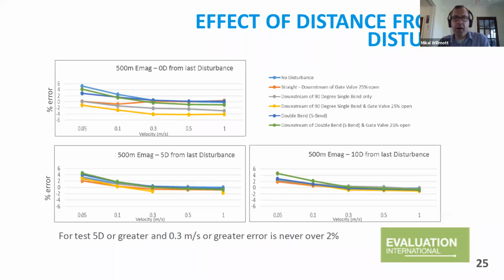And then they did it 5 diameters down. So this would have been 2,500 millimeters down from the last disturbance. And then they did it 10 diameters down from the last disturbance. And what we see is that when you go from 0D to 5D, there's quite a difference. The results at 5 diameters downstream from the disturbance are a lot better than at 0 diameters. So it appears that meters like to be socially distant. Now, when you get from 5 diameters down to 10 diameters, there's not really much difference.